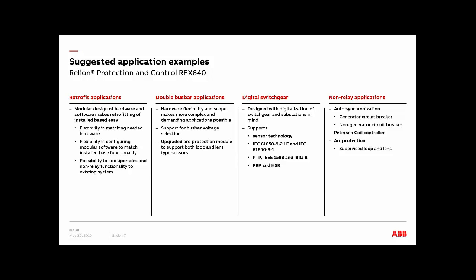For double bus bar applications, you can have hardware flexibility, which you could develop schemes based on GOOSE or high impedance protection, as I mentioned before. If you have digital switchgear, you can have the sensor technology available to you. You can have the PTP, Precision Time Protocol, IEEE 1588, and IRIG-B, as well as the PRP and HSR communication as well.